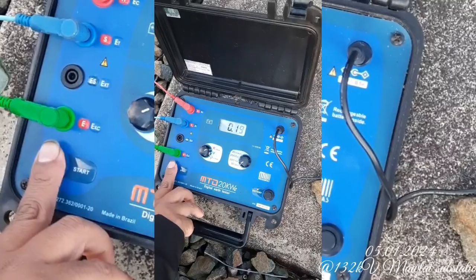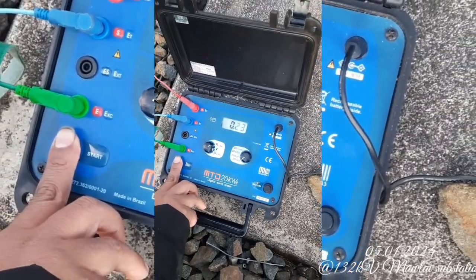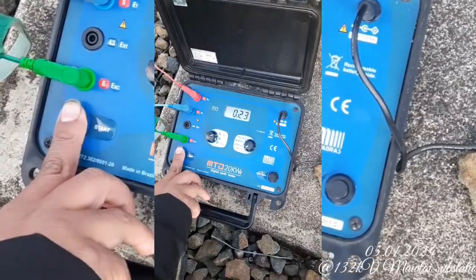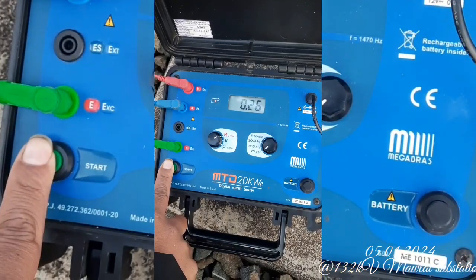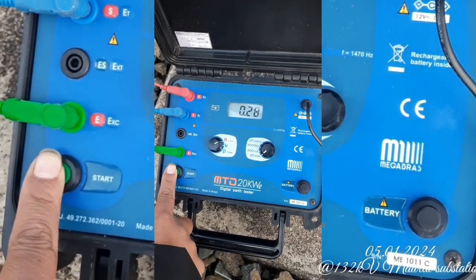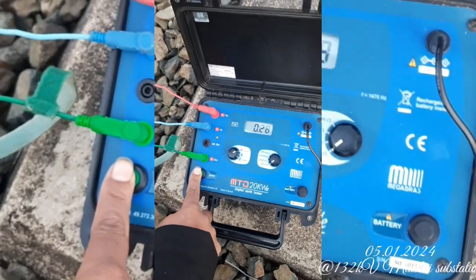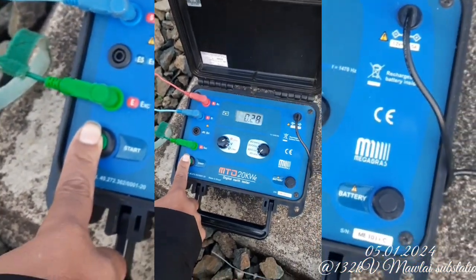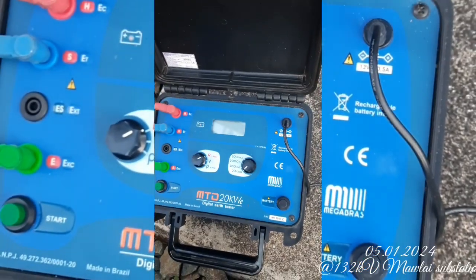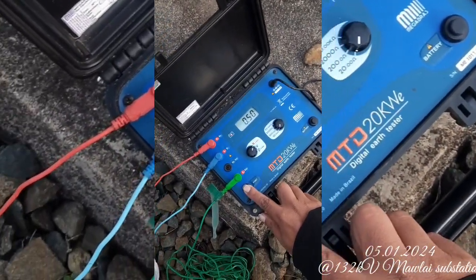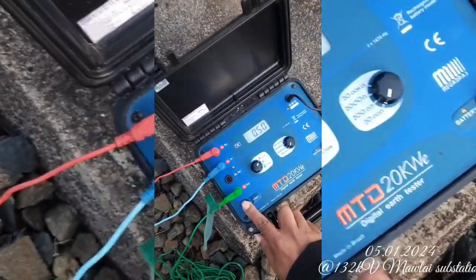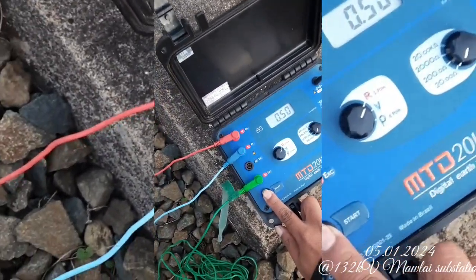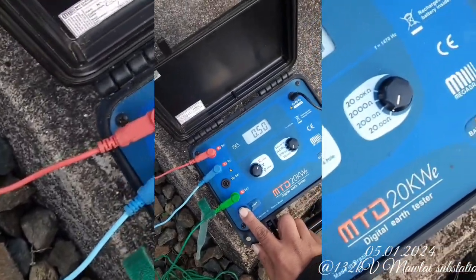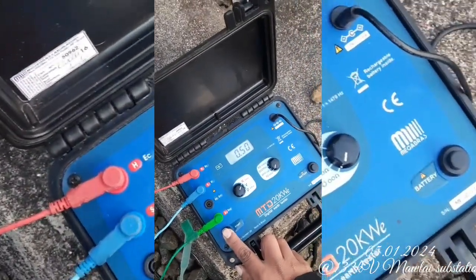So the CR value is 0.23, which is a very good resistance value. This is how we are getting the reading, and it will keep increasing if we reduce the distance. In this case, I reduced the current electrode to 10 meters and the voltage electrode to half of it, 5 meters, and the reading is 0.5. If I reduce the distance by half, the resistance will also increase by the same proportion.